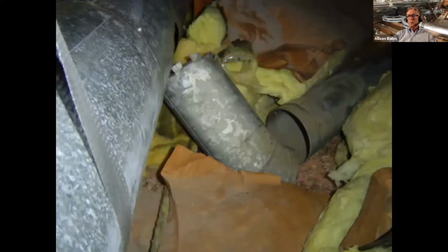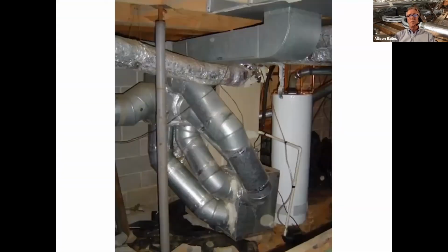Hard pipe, of course, some people think is the answer. This was a hard pipe system I took apart. Well, I didn't take it apart. I took the insulation off. It fell apart by itself. The insulation was what was holding it together. Here's a hard pipe system. Again, very confusing. I think the reason for this is somebody didn't want to take the stuff back to the shop with them, or they wanted to use up a bunch of fittings.